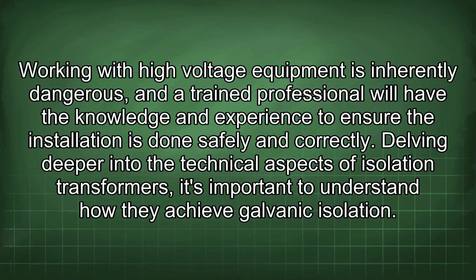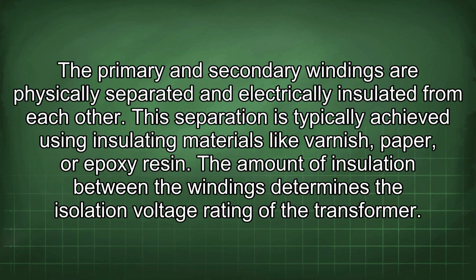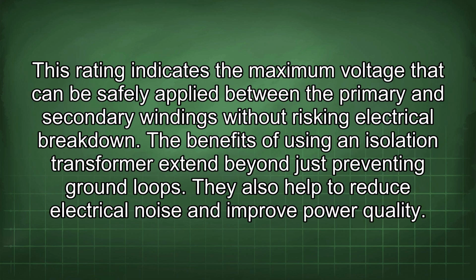Delving deeper into the technical aspects of isolation transformers, it's important to understand how they achieve galvanic isolation. The primary and secondary windings are physically separated and electrically insulated from each other. This separation is typically achieved using insulating materials like varnish, paper, or epoxy resin. The amount of insulation between the windings determines the isolation voltage rating of the transformer. This rating indicates the maximum voltage that can be safely applied between the primary and secondary windings without risking electrical breakdown.